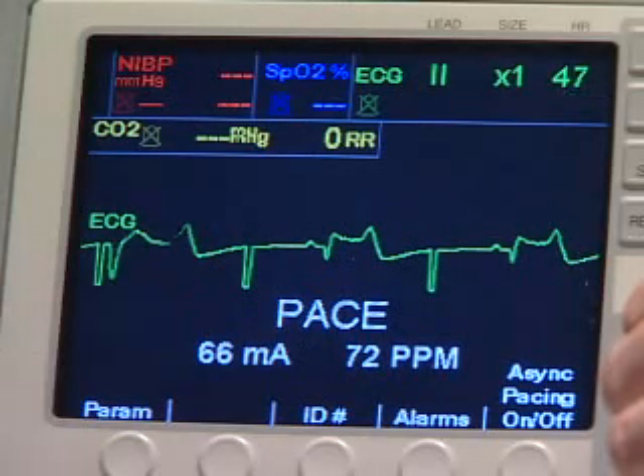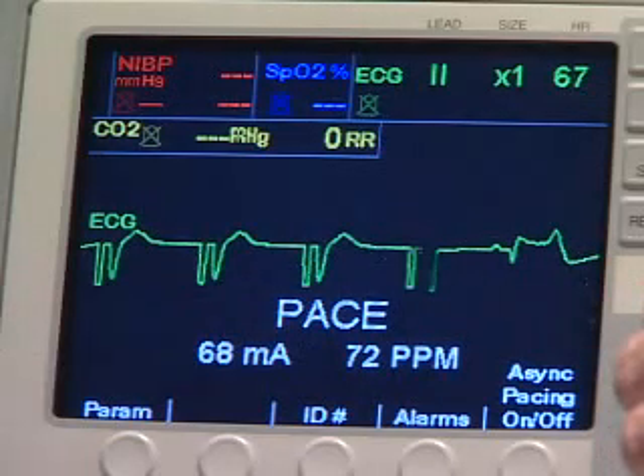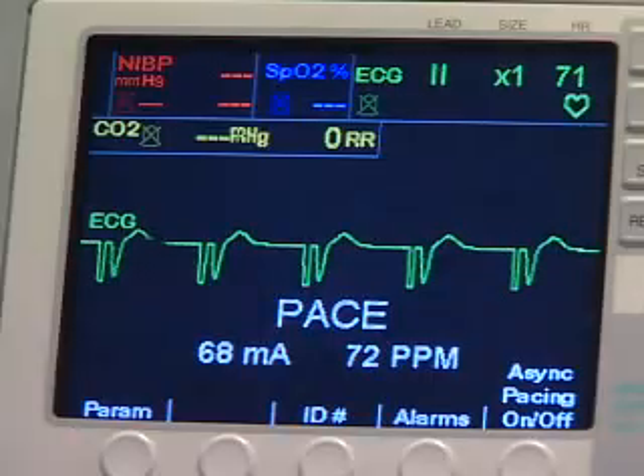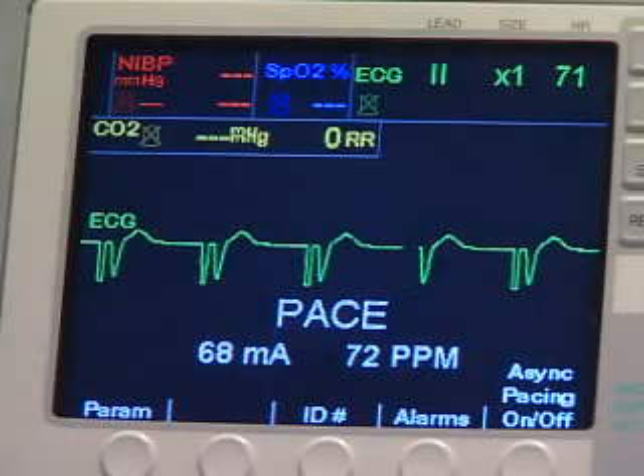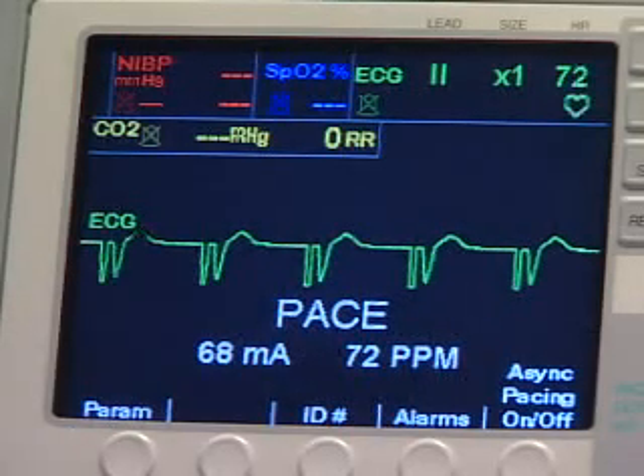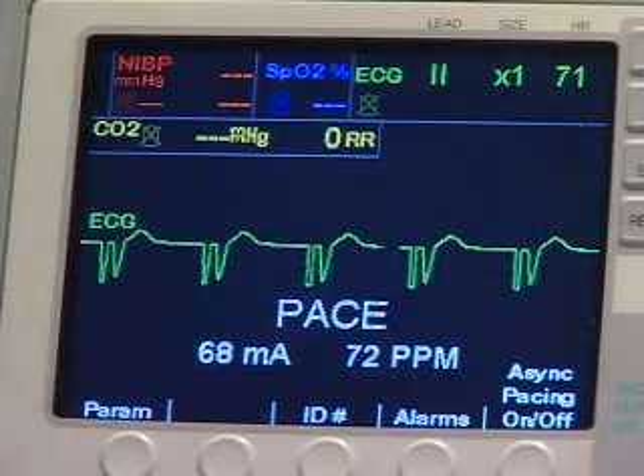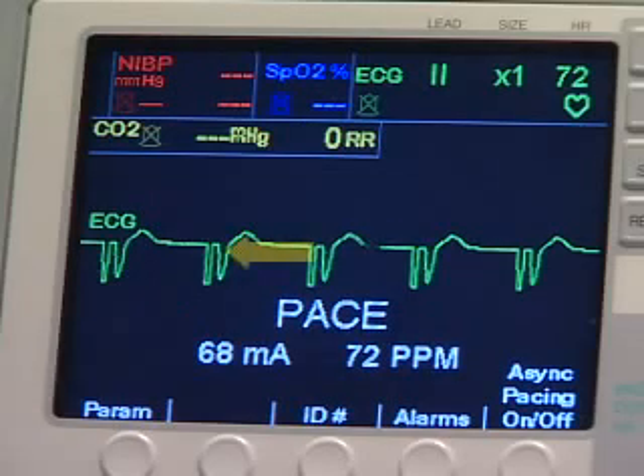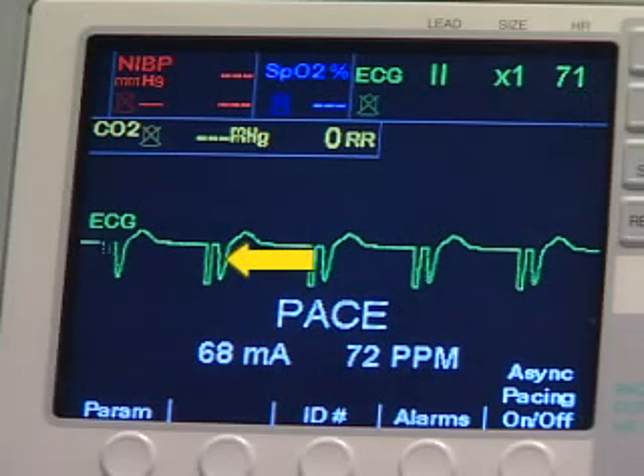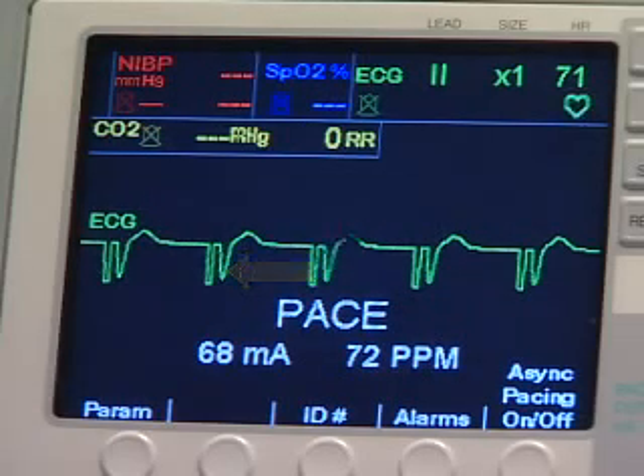The pacer increases or decreases by 2 pulses per minute on the display when you turn the knob. Increase the pacer output milliamps until you see capture, when the heart is being paced by the unit rather than the patient's own pacemaker. Capture is indicated by a downward spike on the E-Series display.